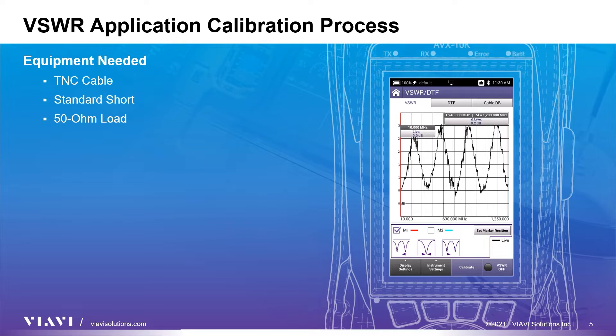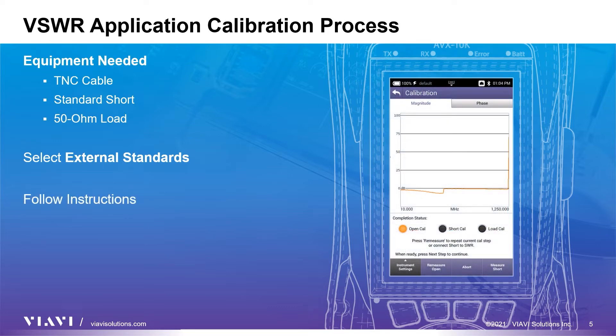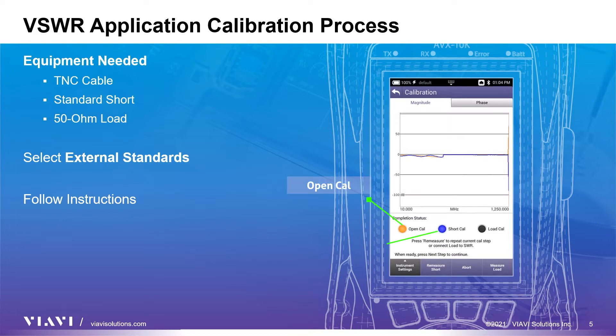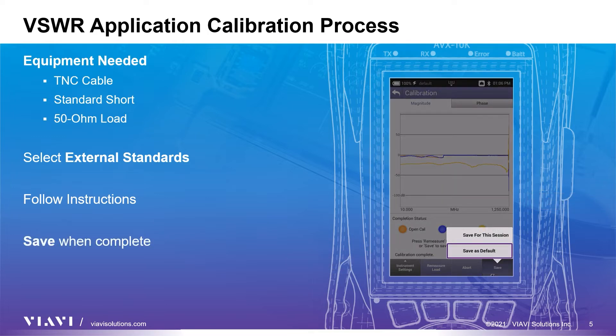If you purchased a kit, you should have this equipment. Start the calibration procedure, select external standards, and then follow the instructions provided to measure an open with cable attached, then measure with a standard short, then measure with the 50 ohm load. Finally, save the measured values using the save as default option.